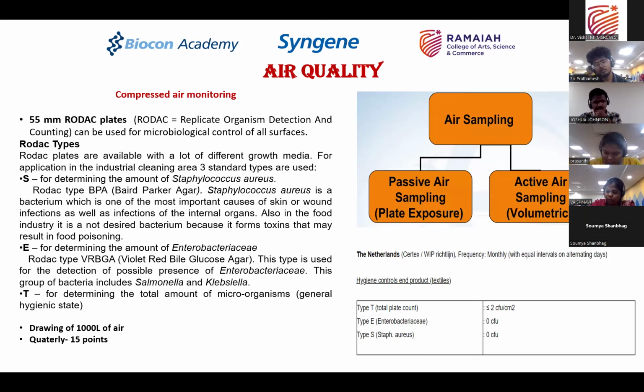Passive air sampling means whatever RODAC media plates are there will be exposed in the area for 4 hours. Then they will be closed and kept in an incubator for incubation, so that the organisms will grow, multiply, and form colonies. In active air sampling, the air will be forced on the plate, and then the plates will be closed and kept for incubation, and the colony forming units will be counted, and the results will be monitored. So this is about air quality.